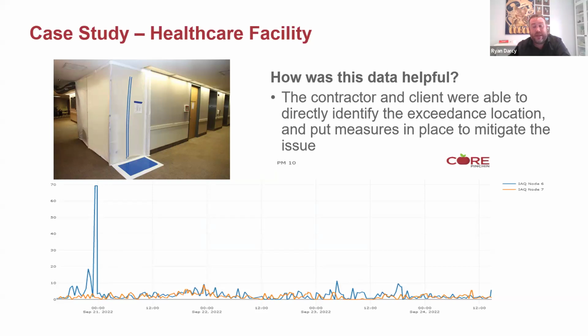Since we had the ActiveIAQ system in place, users and stakeholders got notifications when the parameter was outside the recommended range. In real time, they got alerts, determined something was going on with the construction activity, reviewed it, and found a deficient work process causing the spike. They were able to adjust that work activity in real time and stop the issue, which could have put building occupants at risk.